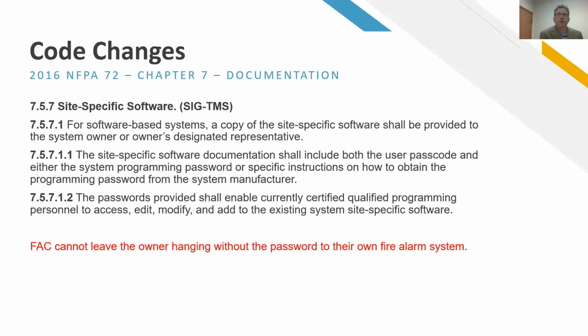All right, here's a new requirement, and it's actually kind of cool. Now we're into the NFPA 72 changes, which make up most of the fire code changes. That's the standard that tells you how to put in your system, maintain it, and deal with it once your devices are in place. This is a pretty cool section that's really great for owners, because it addresses the situation where you hire a fire alarm contractor, they take care of you, they change all the passwords on the panel so only they can program it, and then they don't want to play nice and won't hand over the password when it's time, if you decide to go to a different vendor. This gets to be a real sticky situation, and sometimes the authority having jurisdiction has to get involved and knock on the door of that fire alarm contractor to say, hey, you've got to cough up those passwords.